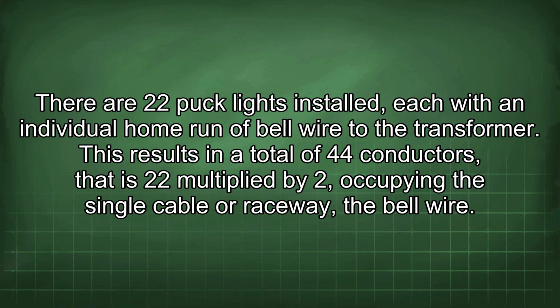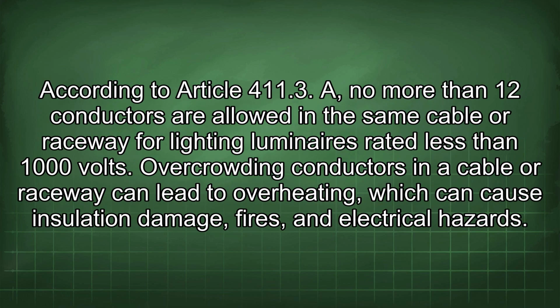This results in a total of 44 conductors, that is 22 multiplied by 2, occupying the single cable or raceway, the bell wire. According to Article 411.3, no more than 12 conductors are allowed in the same cable or raceway for lighting luminaires rated less than 1000 volts. Overcrowding conductors in a cable or raceway can lead to overheating, which can cause insulation damage, fires, and electrical hazards.